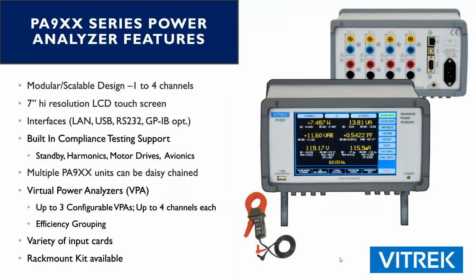Here's some more detail on the PA 900 family. There's the 900, the 910, and the 920. All of the cards store their own calibration data, so you could swap in whatever you need, from a high current card to a high bandwidth card to a higher voltage card. The most common is typically the AD, which would be our most accurate version with a dual shunt. It's got a 1 amp and 20 amp internal shunt. All of these will go to 500 harmonics, that's standard, and you can add channel cards as needed. It takes about 5 minutes to install, and each chassis will hold 4 of those cards.